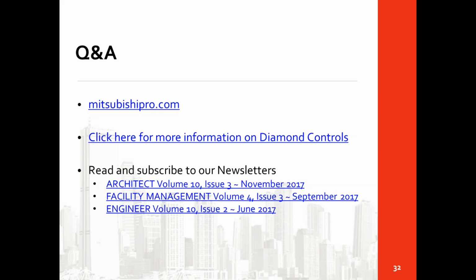You also now have the ability to look at trend logs, one of the most valuable resources for building engineers, since they can identify and look back historically at the building's performance. So if a modification or additional capacity is needed, they can make an informed decision based on what the building has actually done. Another benefit is resale value—a building with a modern control system becomes a much more attractive investment than one with no controls or limited controls.